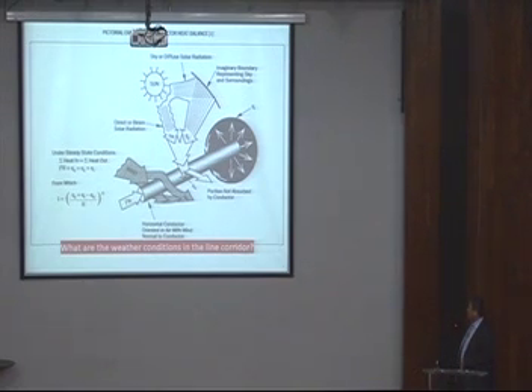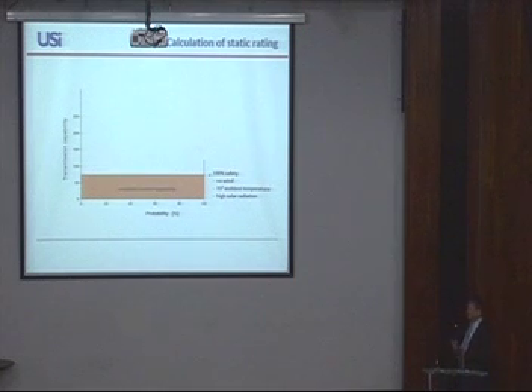What are the weather conditions in the line corridor which allow us to use this formula? How do we get to that? The designers have solved the problem for the transmission line in a quite easy way. They said, okay, we don't know what's happening in the line, so we take conservative assumptions. The most conservative assumption would have been that there's no cooling from wind. This is the highest temperature of the year, 35. In some areas we have 40 or 30 or 25, depending on where on the globe you are. And assuming we have maximum solar radiation, I think in Brazil you use 1,000 watts per square meter.